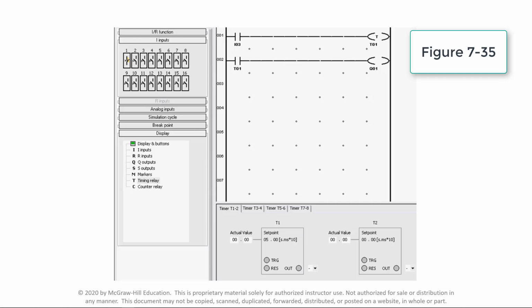This video demonstrates the operation of a PLC programmed on-delay timer. This application calls for the pilot light to turn on any time the pressure switch closes for a sustained period of 5 seconds or more. The pressure switch is hardwired to input I3, address I03. The pilot light is hardwired to output Q1, which is address Q01. The associated ladder logic program has been entered using the front keypad and LCD display.